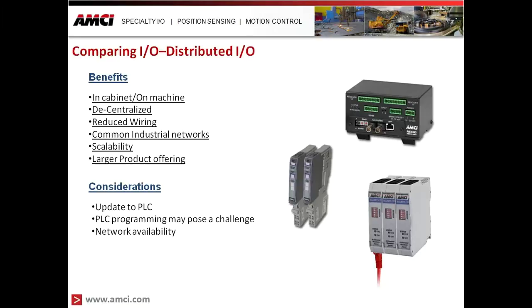Some considerations with distributed IO include the update rate to the PLC. Because you're going through a network connection, there are communication limitations to be aware of. If you have very high-speed inputs or outputs that need to be monitored or controlled, you may want to put those in your PLC rack rather than a distributed IO solution.